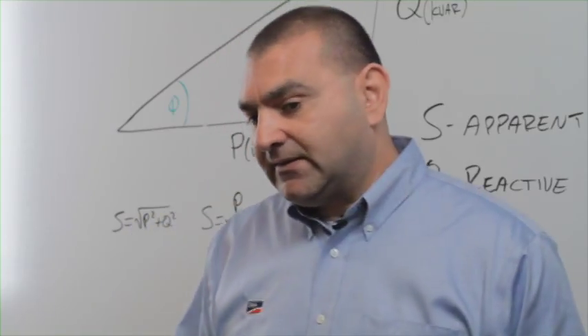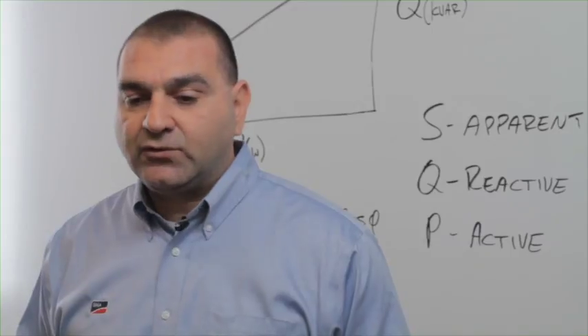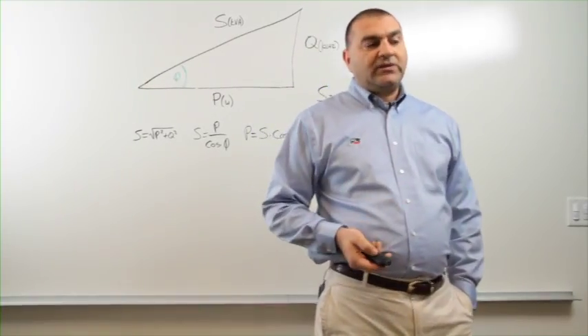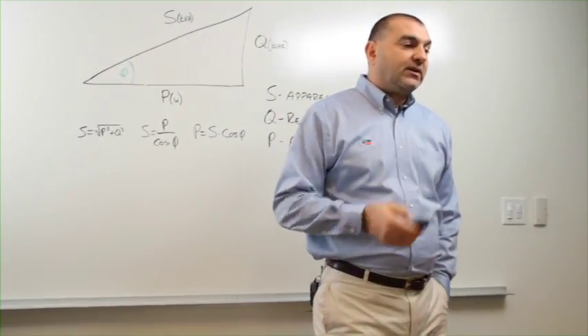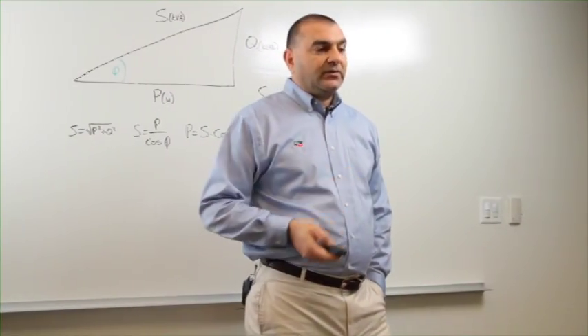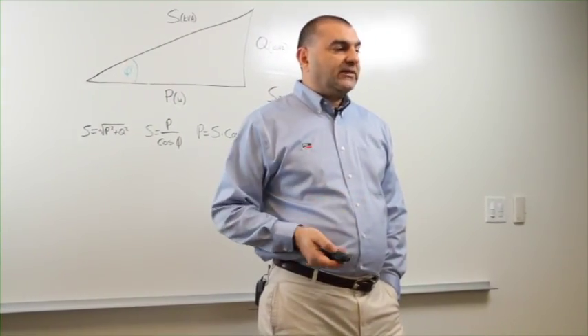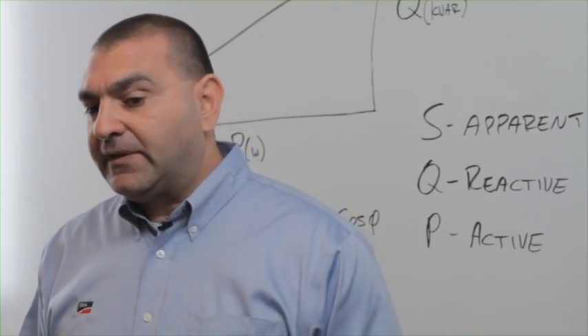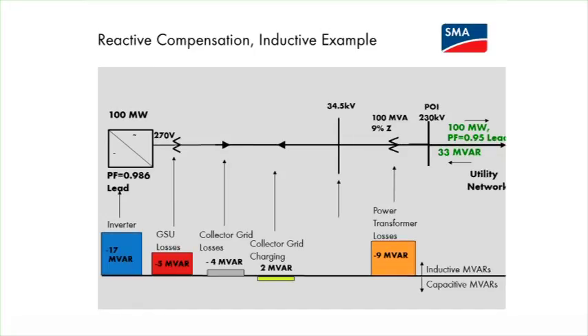So this is a simple example. It's not meant to be a true representation of a power plant, because that usually requires studies by consultants or specialty firms that can do these plant studies. But just for illustration purposes, if I'm required to provide 100 megawatt as a PPA, for example, at the point of interconnection, with the 0.95 lead power factor, this can lead to a 0.986 power factor requirement at the inverter level.